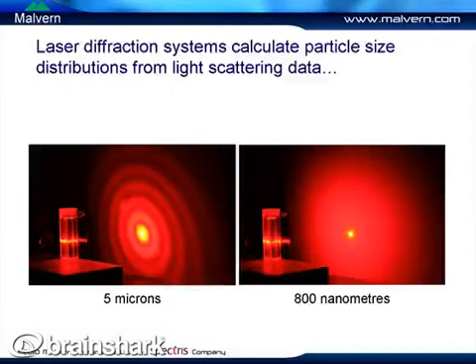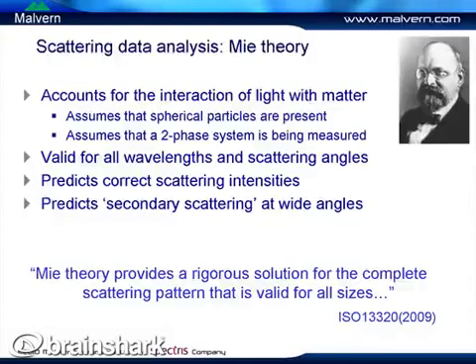The optical models we use to predict scattering behavior require input information. The main model used in laser diffraction is the MIE scattering model, which accounts for the interaction of light with matter. It makes some key assumptions: all particles are assumed to be perfect spheres, so even non-spherical particles are interpreted as an equivalent sphere, giving an equivalent spherical diameter. MIE theory also assumes a two-phase system, so for mixtures of materials, some approximations are necessary.